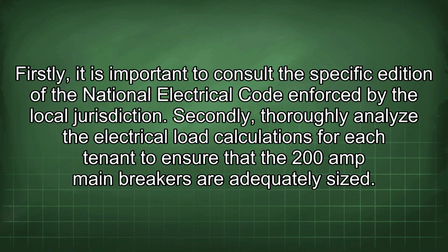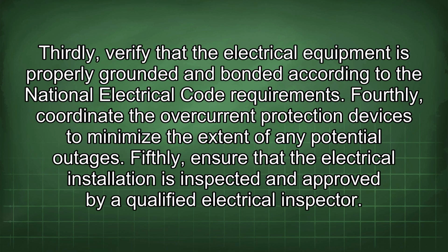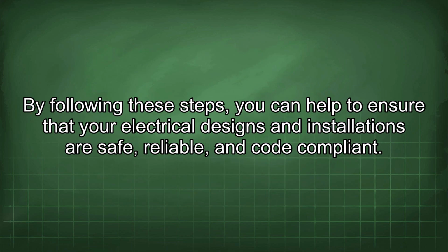Firstly, it is important to consult the specific edition of the National Electrical Code enforced by the local jurisdiction. Secondly, thoroughly analyze the electrical load calculations for each tenant to ensure that the 200 amp main breakers are adequately sized. Thirdly, verify the electrical equipment is properly grounded and bonded according to the National Electrical Code requirements. Fourthly, coordinate the overcurrent protection devices to minimize the extent of any potential outages. Fifthly, ensure that the electrical installation is inspected and approved by a qualified electrical inspector. By following these steps, you can help to ensure that your electrical designs and installations are safe, reliable, and code compliant.